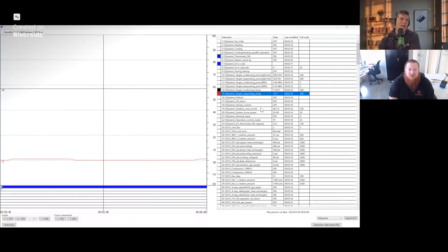It's saying that we've hit high pressure, high temperature on the discharge line of the actual compressors. And what do we know about high discharge? High discharge is a bad thing, especially when it gets up into the ranges to actually trip an error code. It's happened 3 times within 60 minutes. It's a bad thing.